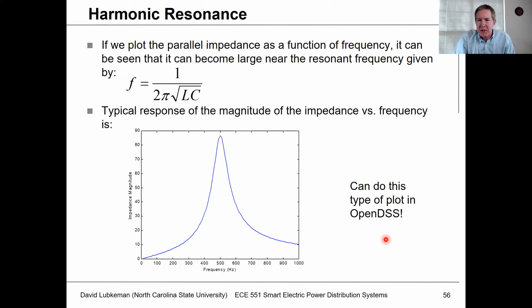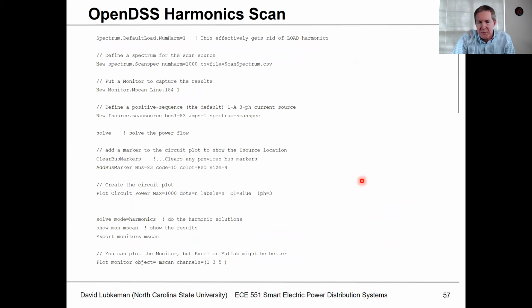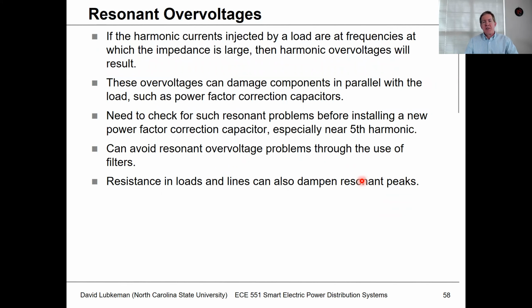OpenDSS can actually plot this resonant response. I've just got some sample code here, but once you put in your line model, you can also get OpenDSS to work in the harmonic domain. And if you give it the right commands, it'll do this harmonic scan for you and figure out, for a given harmonic source, what happens to the voltages in the circuit as a result. So anyway, this is something we always have to be on the watch for. If you have harmonic currents injected by a load at frequencies where the system impedance is large, then we have the potential for some really high harmonic overvoltages, called resonant overvoltages. And this can damage components that are in parallel. So if you have certain loads, these could be damaged by resonant overvoltages.